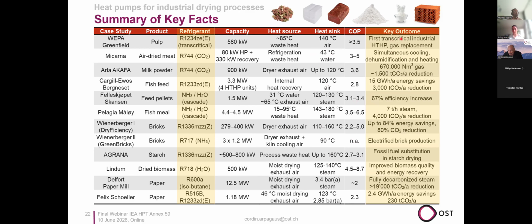The transcritical heat pump is something unique. For the dryer, we have simultaneous cooling, dehumidification, and heating. For the spray dryer, we can reduce a lot of fossil fuel use, giving energy savings and CO2 reductions. We can generate steam too, as shown in the steam heat pump examples. This brick production case is fully electrified, so electrifying the processes is a major outcome and goal, reducing fossil fuel dependence and so on. This is a summary of that.